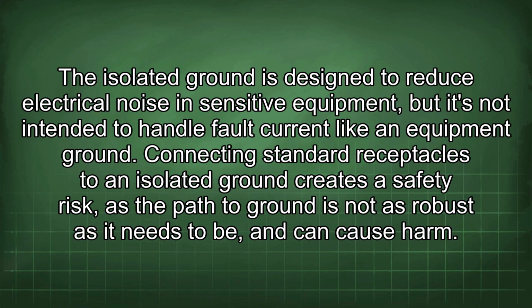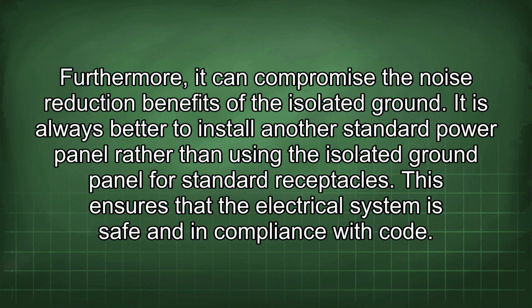The isolated ground is designed to reduce electrical noise in sensitive equipment, but it's not intended to handle fault current like an equipment ground. Connecting standard receptacles to an isolated ground creates a safety risk, as the path to ground is not as robust as it needs to be and can cause harm. Furthermore, it can compromise the noise reduction benefits of the isolated ground. It is always better to install another standard power panel rather than using the isolated ground panel for standard receptacles. This ensures that the electrical system is safe and in compliance with code.